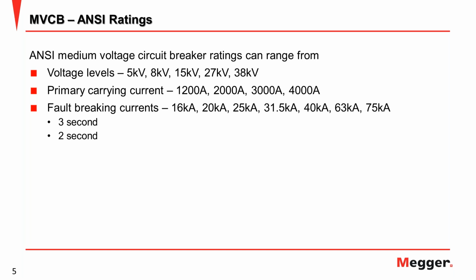And also primary carrying current. There are 1200 A, 2000 A, 3000 A, 4000 A, and maybe more than 4000 A you can find in your country, but mostly the maximum is 4000 A in many applications. The primary current is the maximum current that can flow through the breaker continuously. Usually the design engineer chooses the breaker based on this primary carrying current and voltage level, and after they calculate everything they can define this type.